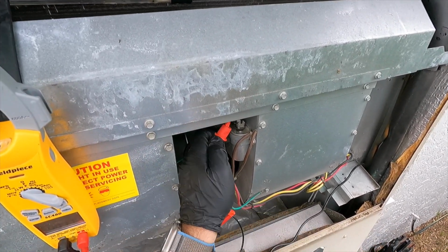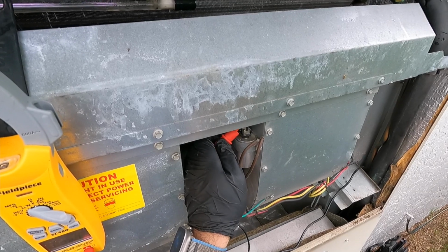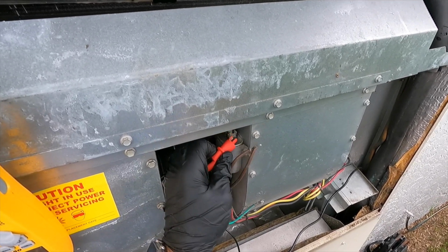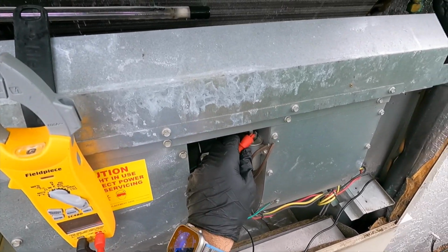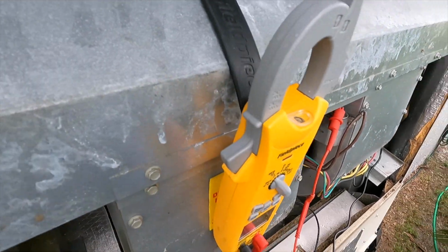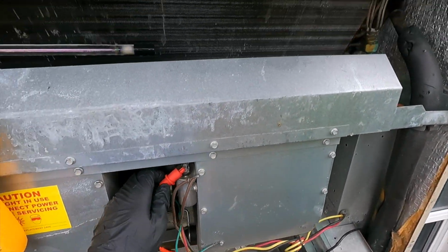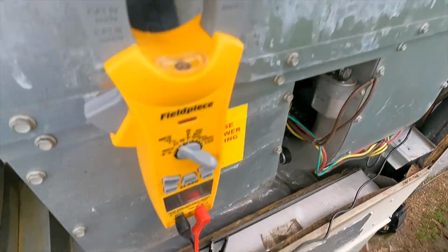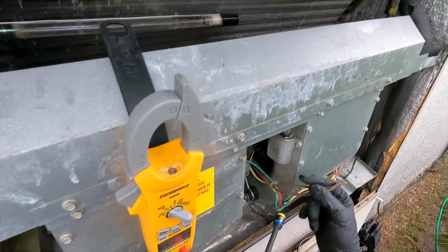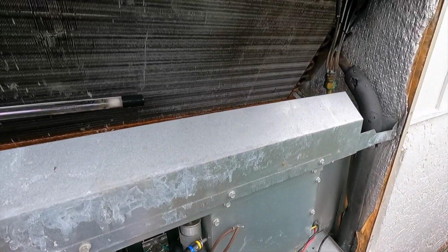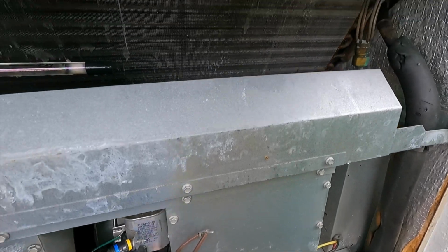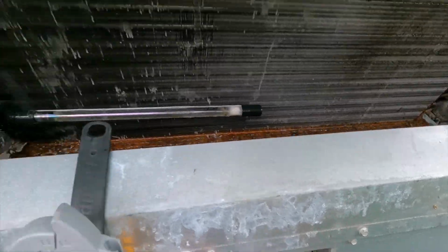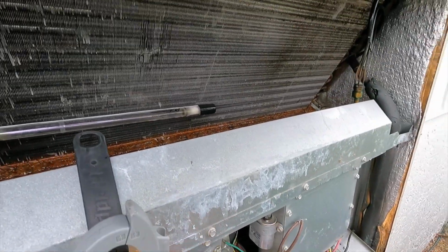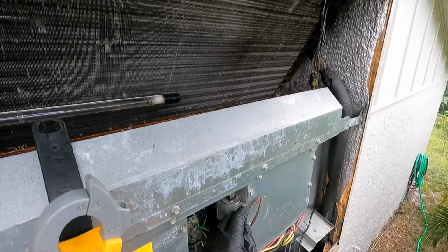All right, so we're gonna test. This is a single run capacitor for the fan or the blower motor. So we're gonna go ahead and just check the microfarads on it. I don't see what the rating is on it, but looks like it's installed backwards. So let's see if we can read that real quick. I was reading 3.35 microfarads, so plus or minus 3%, so we're almost 50% low. I'm gonna recommend he replaces that.